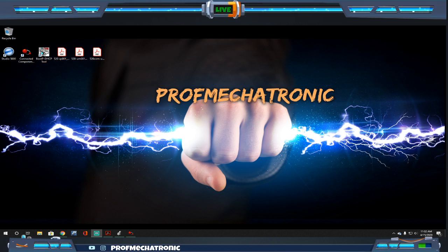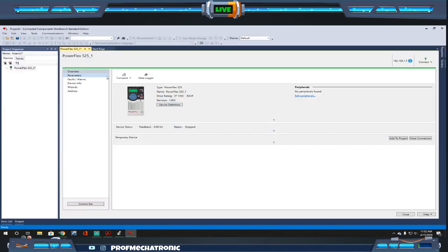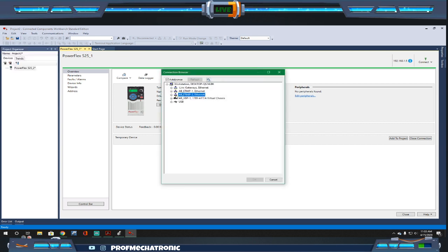Question just came in: what cable is used to connect to read the drive from the PC when using Connected Components Workbench? The nice thing with Connected Components Workbench is you have the ability to do a few different things. The Allen Bradley PowerFlex 525 only has an Ethernet type connection, so in this case we'd be using the Ethernet protocol. This here is the Ethernet IP connection to my drive. Other drives outside the 525 series may have a USB connection, and if that ability exists, anything in your RSLinx would show up in this connection browser. For the 525s, Ethernet IP is definitely the way to go.